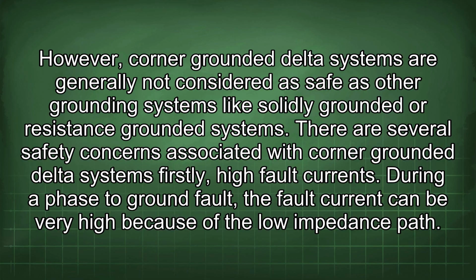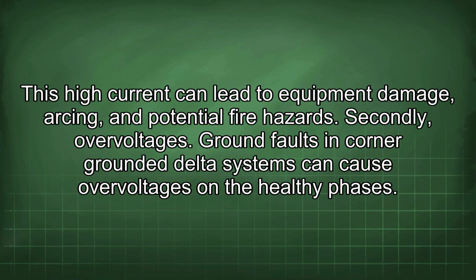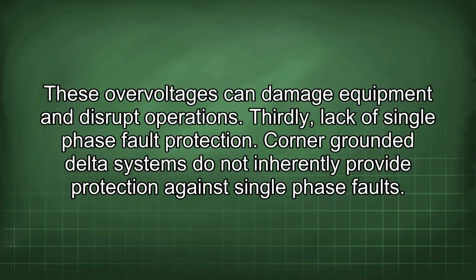Firstly, high fault currents. During a phase-to-ground fault, the fault current can be very high because of the low impedance path. This high current can lead to equipment damage, arcing, and potential fire hazards. Secondly, overvoltages. Ground faults in corner-grounded delta systems can cause overvoltages in the healthy phases. These overvoltages can damage equipment and disrupt operations.